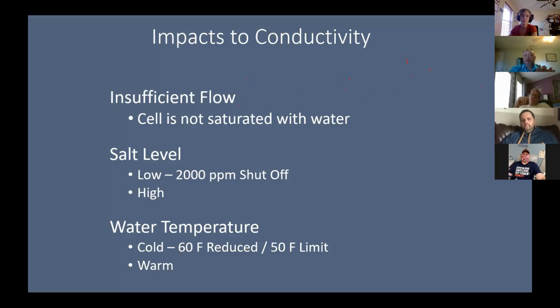Water temperature, as your water temperature starts getting cold around 60 degrees, a lot of systems will start shutting down. 50 degrees typically is your limit where you don't want a lot of chlorine generation operation to take place, because under those conditions, you are wearing out the cell prematurely. If you reduce the output down, if it's still operating, that's the best thing for it. In warm water conditions, no issues at all. Warm water actually creates better conductivity in the water as well.